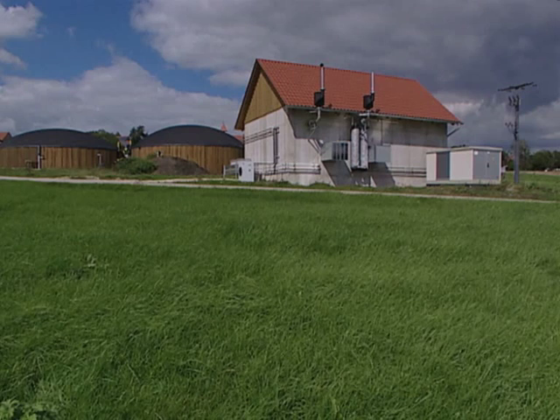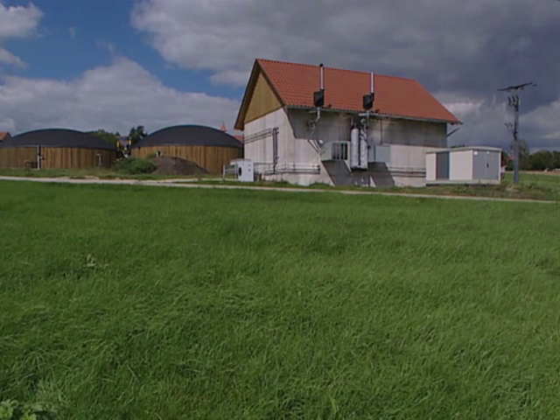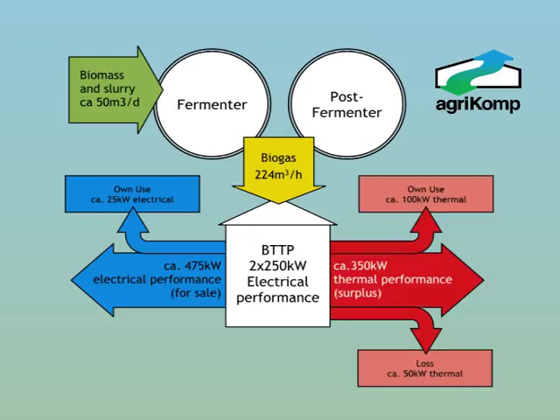It's great to see these sorts of renewable energy schemes being developed and providing something back to our community. The agriKomp technology is extremely energy efficient — the mass balance shows 50 cubic metres per day of inputs produce enough biogas to generate half a megawatt of electricity. The low parasitic load of the plant means that 95% of the electricity is exported to the grid, and there is enough surplus heat for beneficial uses such as drying and pasteurization.